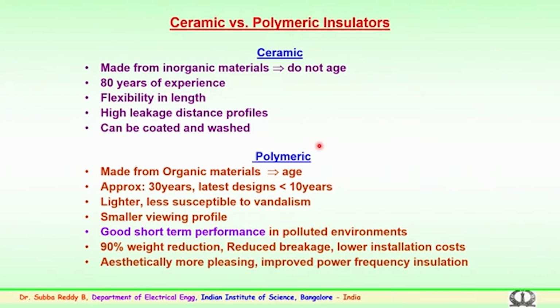So, polymer insulators are made from organic materials, and they age, which is very important. Approximately 30 years at maximum is the period in which this technology has been seen, and the latest designs are slightly less than 10 years old. So it requires a lot of studies, a lot of field data, and a lot of field performance of these insulators so that improvement in design could be carried out. But they are much lighter, less susceptible to vandalism, and have a smaller viewing profile, and good short term performance in polluted environments, as I was telling, which will fulfill the criteria for better performance, particularly for the utilities.